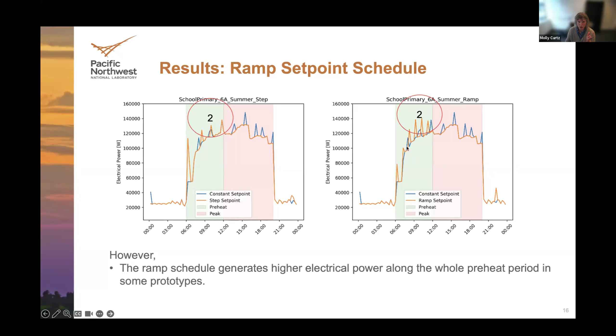On the left side, we have this big spike right at the beginning when we first set the aquastat up to 180. In the other case, we have the ramped schedule. We don't get that big spike right at the onset of the green preheat period, but we still found that subsequent spikes were higher than the spikes we had on the left. So it has to do with the alignment of the overall building electrical load profile and the control of the water heater and the firing of the water heater.